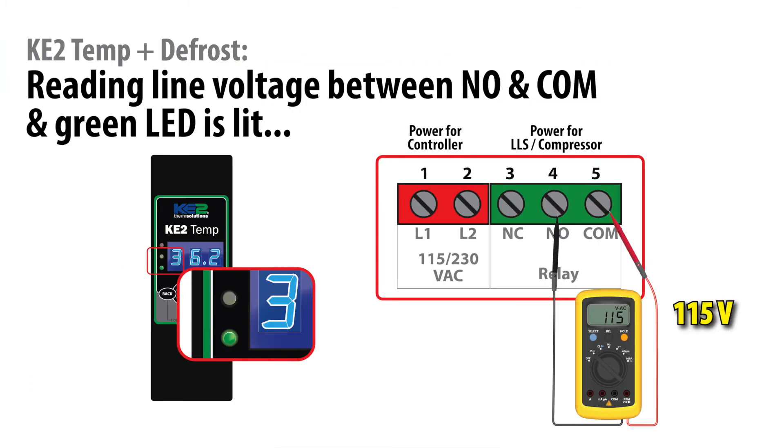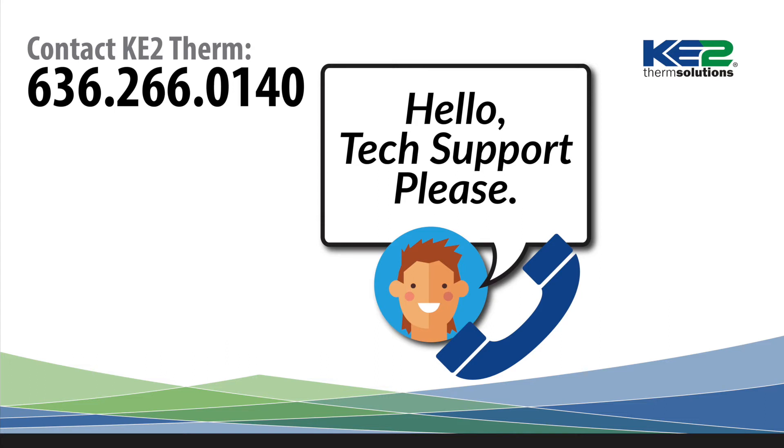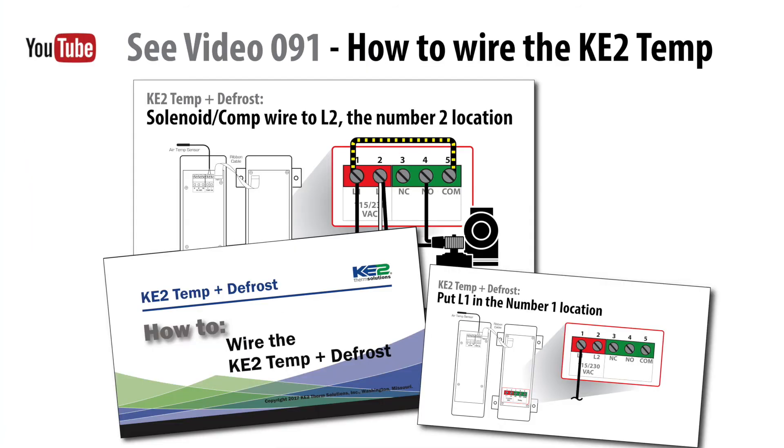If the voltage between the common terminal and normally open terminal of the controller is still reading line voltage and the green LED to the left of the display is on, then usually the controller has been damaged and must be replaced. Contact KE2 Therm's technical support to confirm your findings. If either of the first two voltages are not correct, there is a wiring problem that must be investigated and corrected.